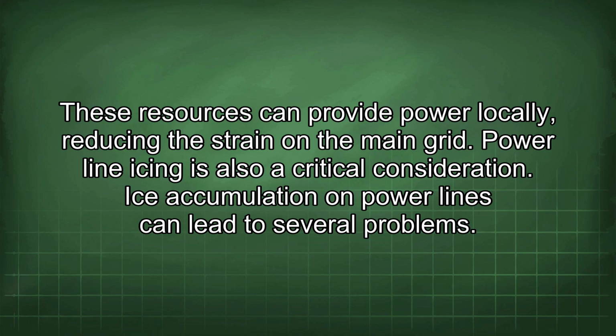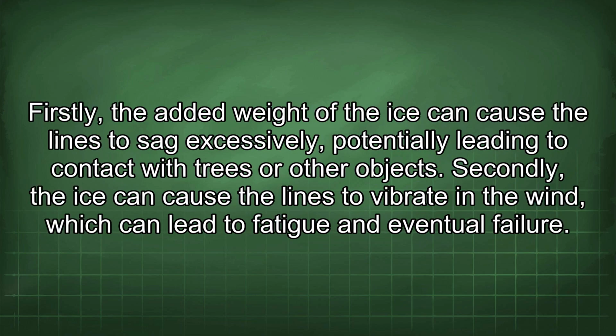Power line icing is also a critical consideration. Ice accumulation on power lines can lead to several problems. Firstly, the added weight of the ice can cause the lines to sag excessively, potentially leading to contact with trees or other objects.